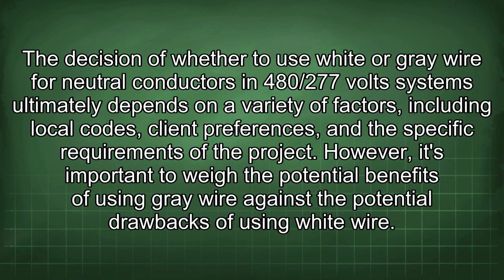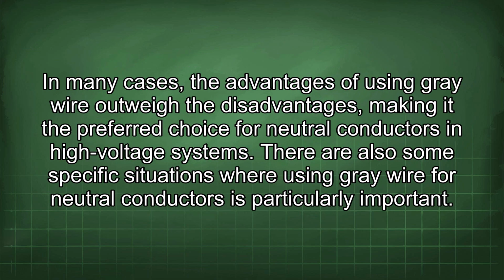The decision of whether to use white or grey wire for neutral conductors in 480/277 volt systems ultimately depends on a variety of factors, including local codes, client preferences, and the specific requirements of the project. However, it's important to weigh the potential benefits of using grey wire against the potential drawbacks of using white wire. In many cases, the advantages of using grey wire outweigh the disadvantages, making it the preferred choice for neutral conductors in high-voltage systems.